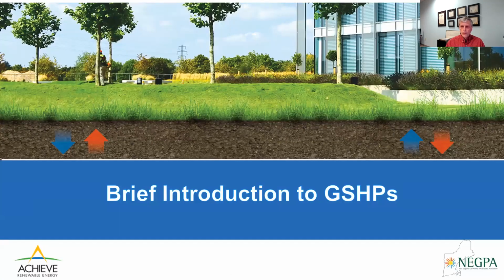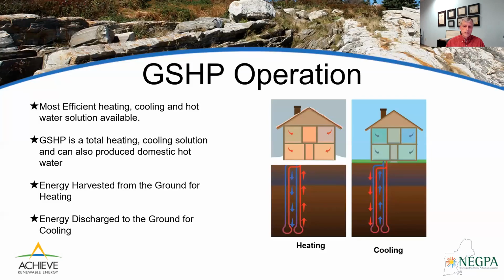So first, a brief introduction to ground source heat pumps and how they work. Very simply, we put a heat exchanger in the ground. The ground heat exchanger, typically at the sites we work at, is a vertical configuration put in with the drilling rig, and the number of borings and how deep they go is a function of the energy demands of the building. As previously pointed out, reducing energy demands reduces the amount of ground heat exchanger we have to install. The ground heat exchanger should be viewed as the fuel for the buildings — it's where we recover the heat used in the winter for heating, and where we place the heat in the summer when we're doing air conditioning.